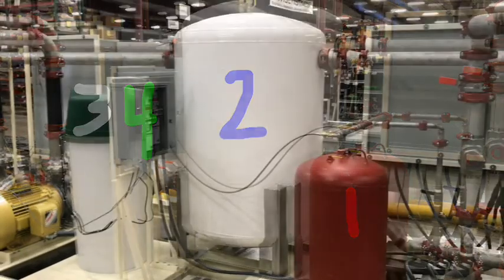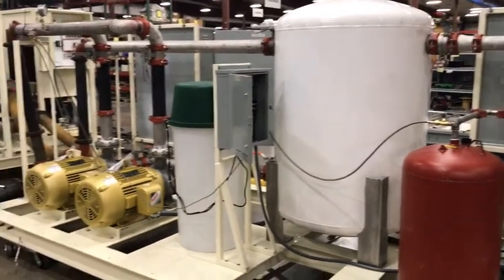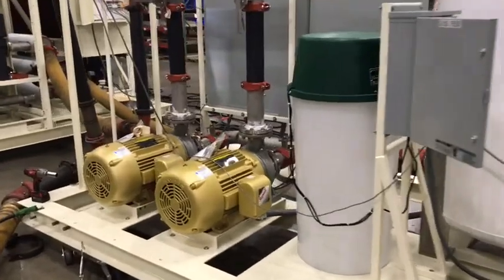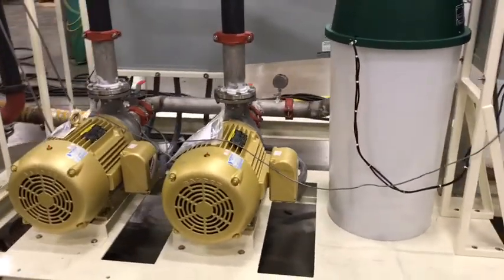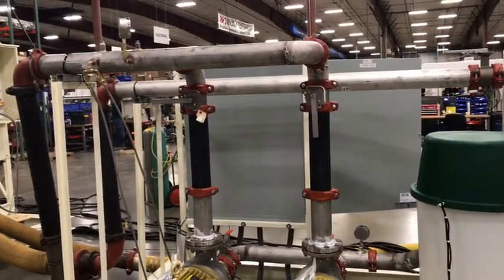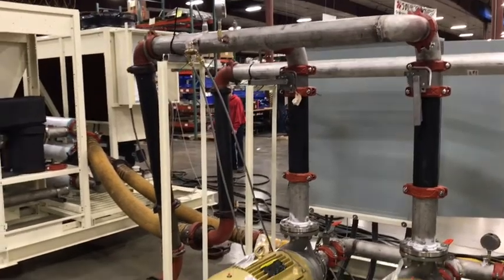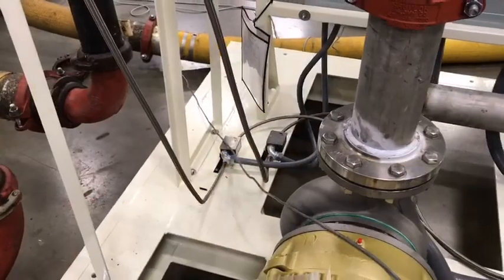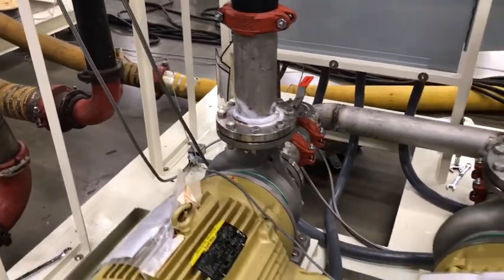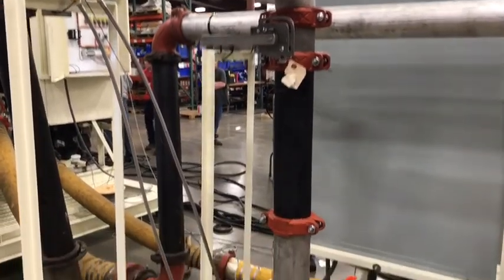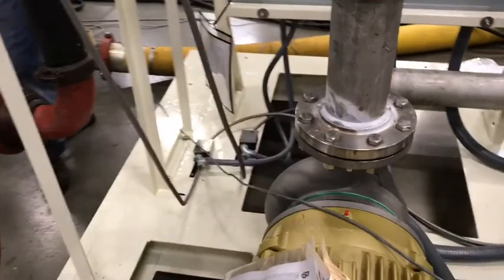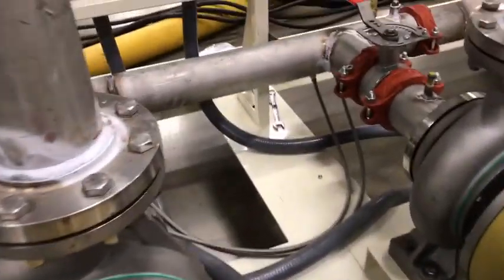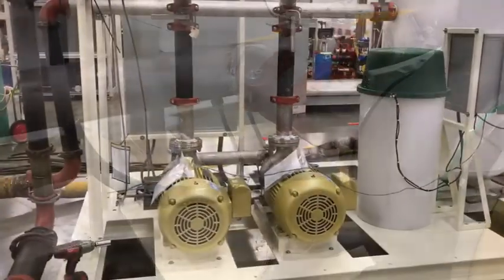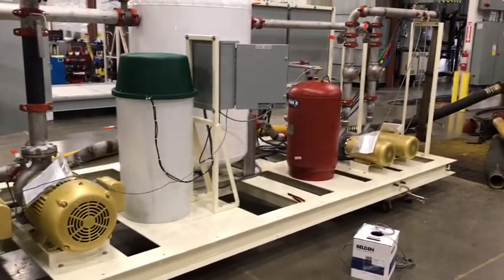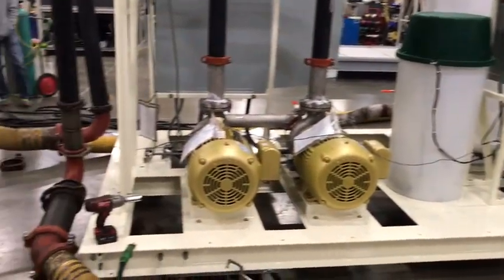We'll continue panning and going to the left, the two larger pumps that are serving both the chiller and a number of spaces. So this is a primary loop set of pumps. Show the supply and return there in the upper left. We'll move in here and see the inputs to the two differential pressure switches. So there's the two hoses that are tied into one side of the pumps coming down. See the differential pressure switches mounted there on the frame. And then those two hose connections are on the other side of the pumps. And just kind of scanning right to get an overall view of the back side of this pump array.